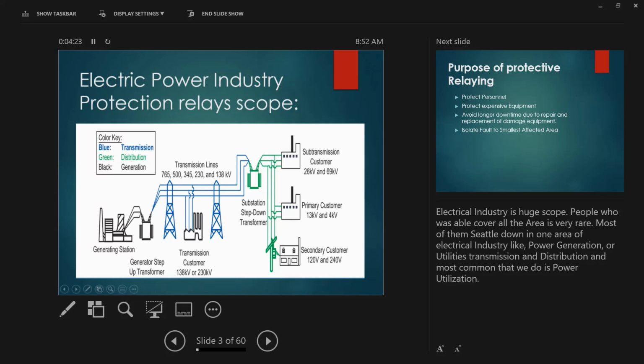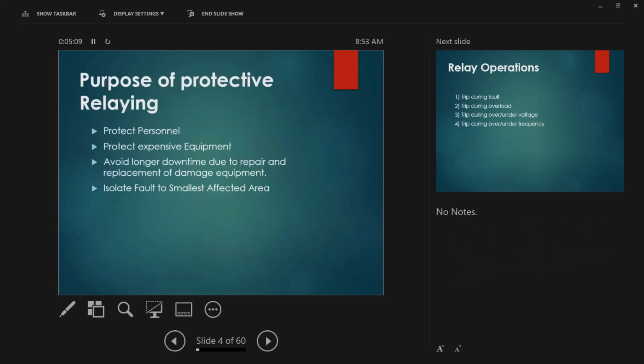So you see the level of voltage over there, 138, 750. So here, of course, low voltage step up there. This transmission line could travel probably 300 or 500 kilometers. And then there's a voltage drop here, your receiving end voltage. So the transformer here will step up again to the ideal requirements for BHP or Rio Tinto. So that's how it works. So you manage everything based on your parameters. Measurement is very important, because if you don't have a proper instrument to measure and decide, how can you tell that you need to step this up to the proper voltage that you want for utilization of power?